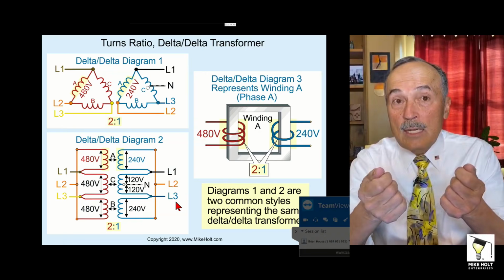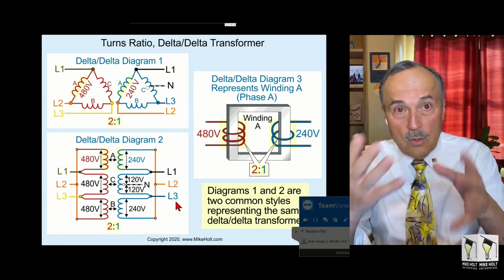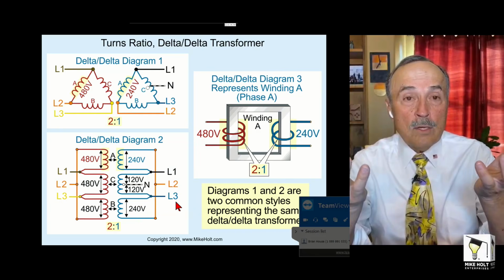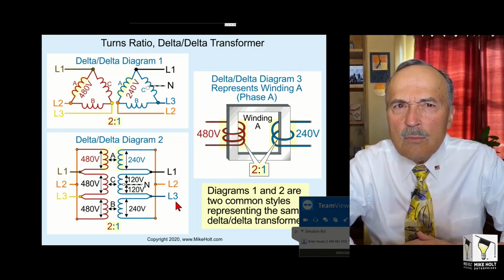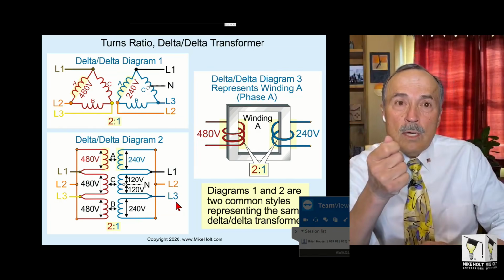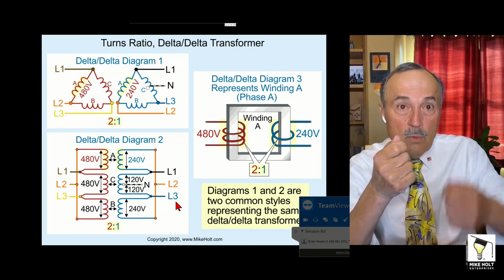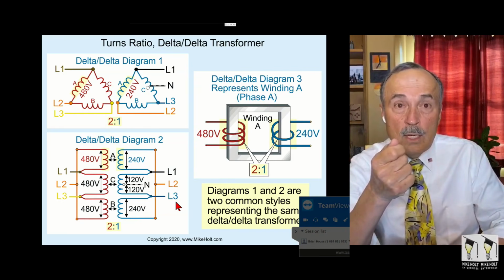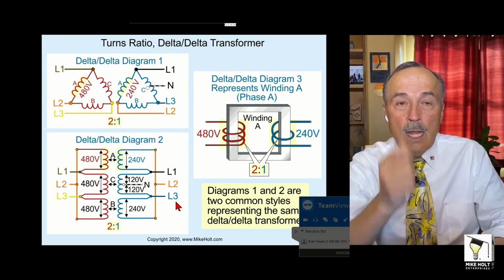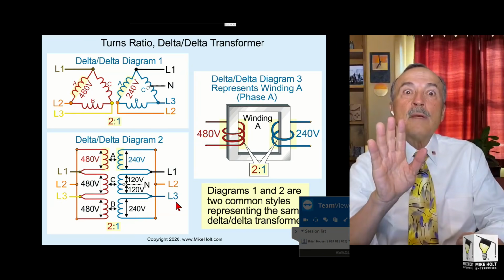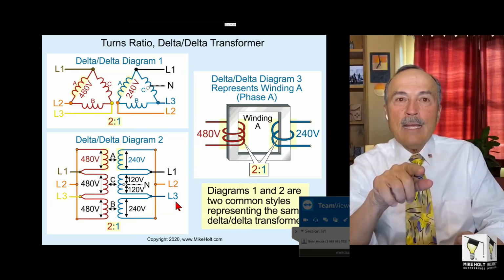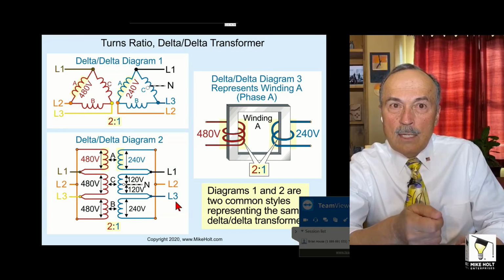Now what you could have done, proper PPE, you know what you're qualified, you could have taken a voltmeter on the transformer and find out, I wonder what kind of transformer I got here. Well, go line 1 to the case with the system bonding jumper installed. You should have had what? 120. Line 2 is like 208. Oh, wait a minute now. I got a high leg. Line 3 is what? 120.